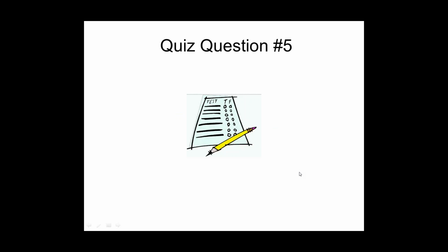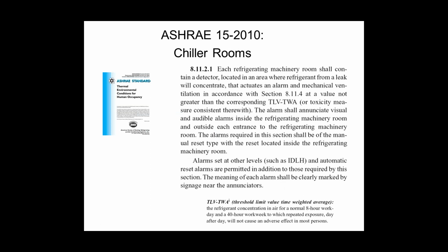All right, last couple things here. ASHRAE 15, which is the refrigerant safety standard. There is, in my mind, one thing that directly relates to the controls guys over and over again, which is that if you have an indoor refrigeration room, such as a chiller room, which comes up a lot, right? Or I guess a supermarket area, compressor deck or something like that. But we'll talk about it as a chiller room. You have to have a refrigerant monitoring sensing system.